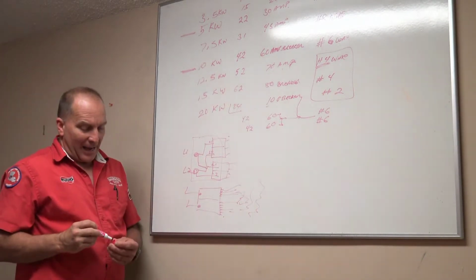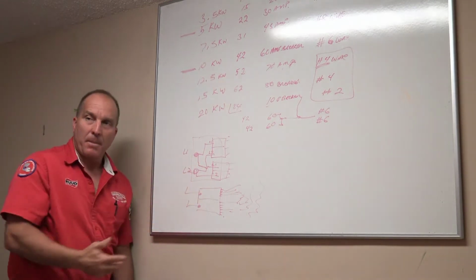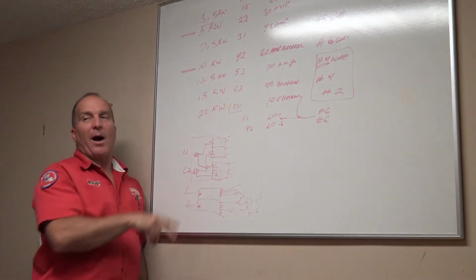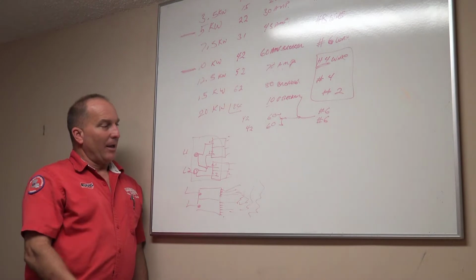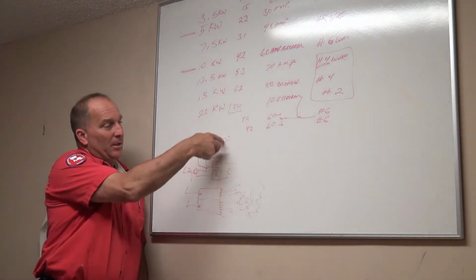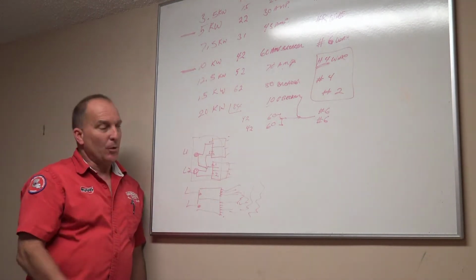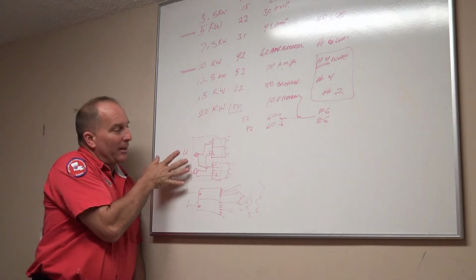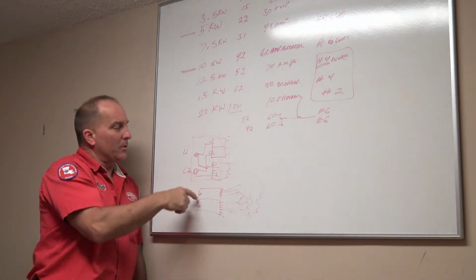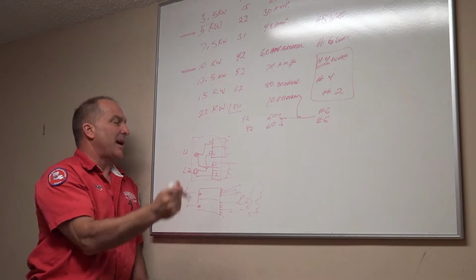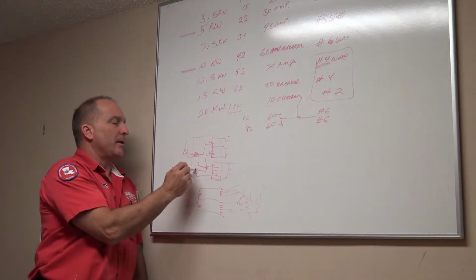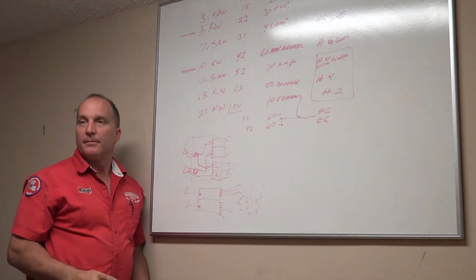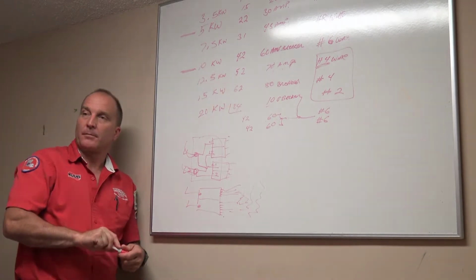So as I was feeding this system, and all I have is a number 2 wire to feed in here, the system comes with 2 60 amp breakers. So I need this terminal plug to plug into all my breakers, screw all those down with two big lugs on here so I can tie two number 2 wires into here is what I need to do. That's how that would work. Okay?